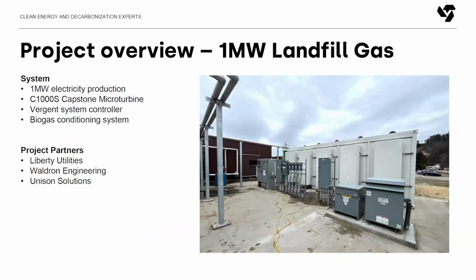The system itself is able to produce 1 megawatt of electricity using a Capstone C1000 microturbine. We incorporated a microturbine interface module controller that's able to control the entire site, providing real-time alerts and real-time data on anything that's going on. It's able to start and stop turbines based on available gas.